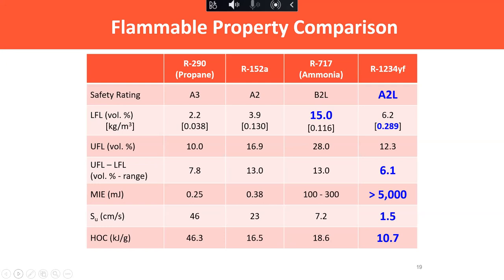So let's look at the propane column in A3 and the 1234YF, which is a very common A2L refrigerant. No matter which of these you're looking at, you can see the difference - whether it's lower flammability limit, it doesn't take a lot, 2.2 of the propane versus 6.2 of the YF. The range between the upper and lower flammability limits is another thing. The minimum ignition energy we've talked about, 0.25 versus over 5,000.